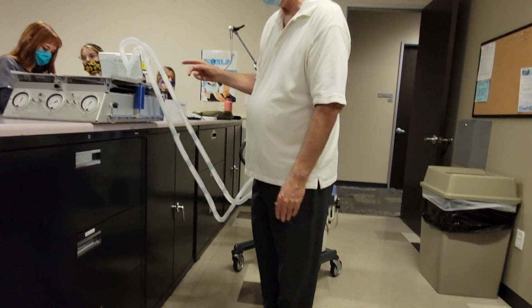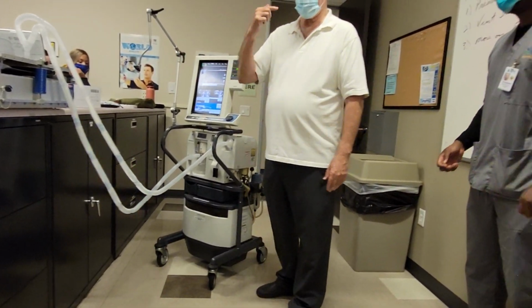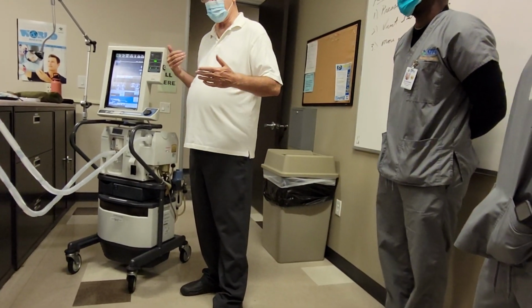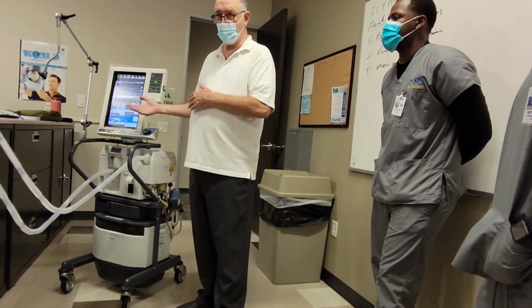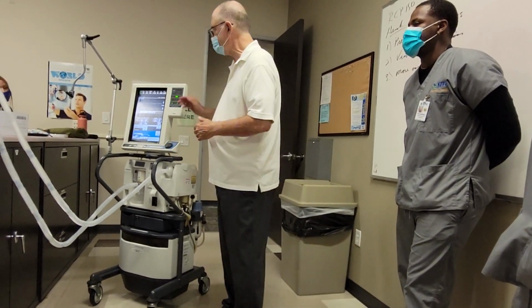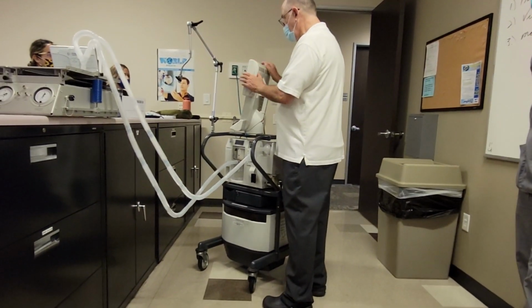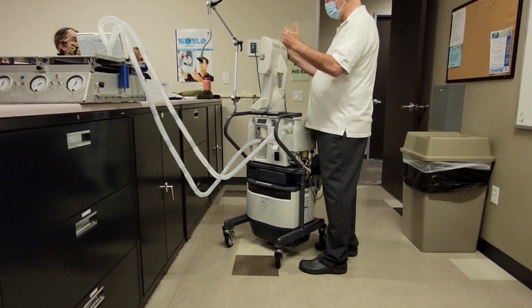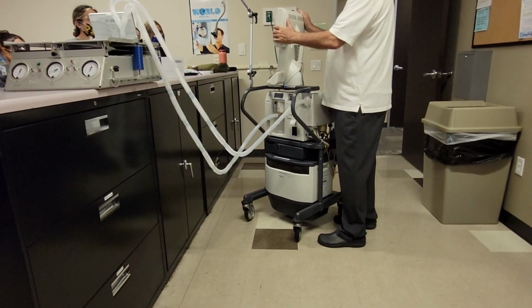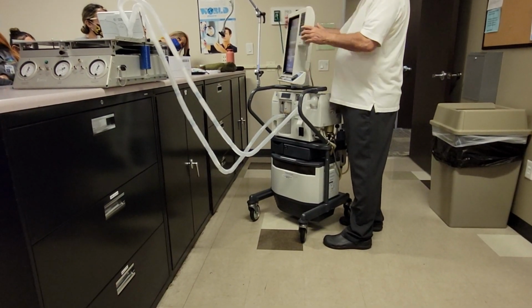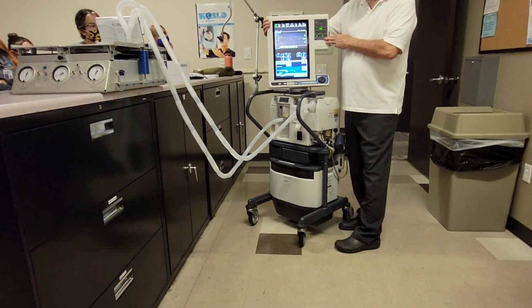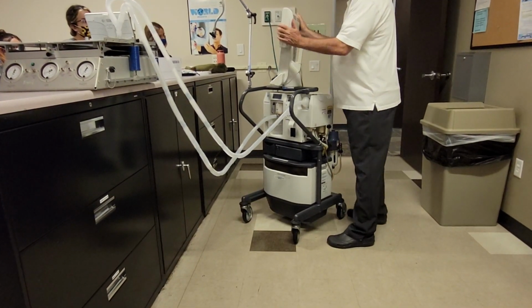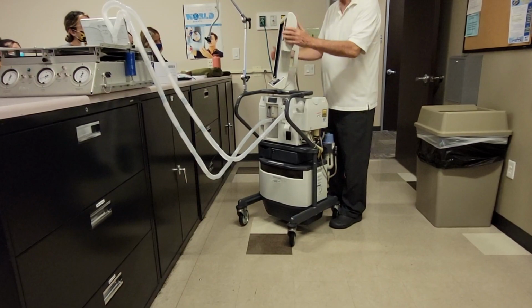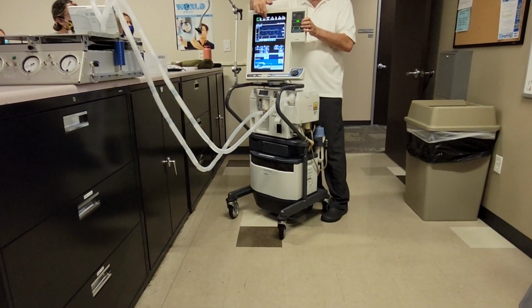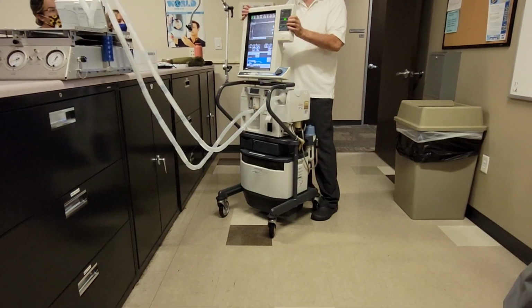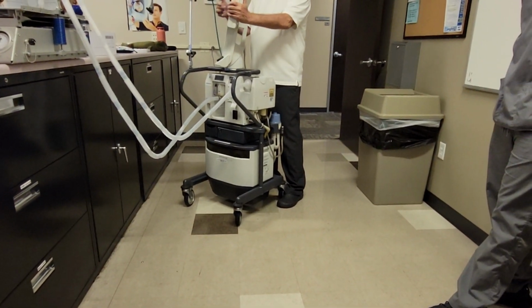Okay. So the ventilator senses that there's gas interruption and gas return. So it begins to cycle according to the way we told it to. Okay? So now you can see the waveforms are being generated by the patient-ventilator interaction. So this is the outcome of those settings. Okay? The graphic user interface has a number of areas. You've got your parameters across the top. Okay? This is the data you're looking to record. Okay? And then the waveforms.